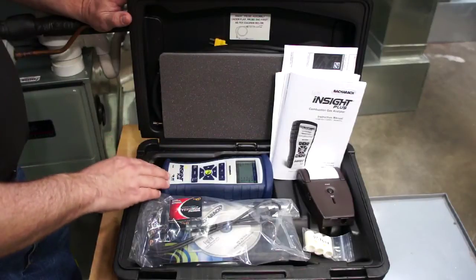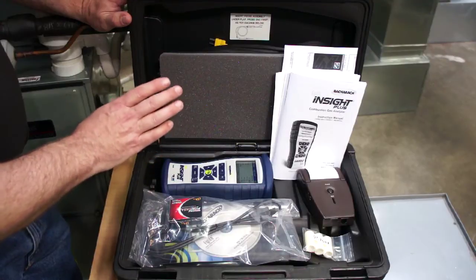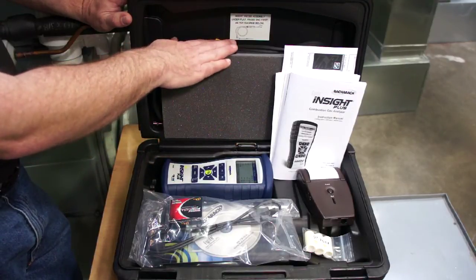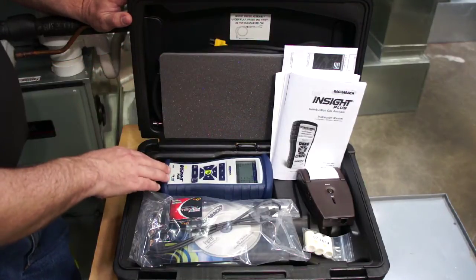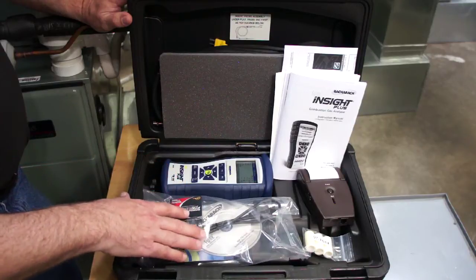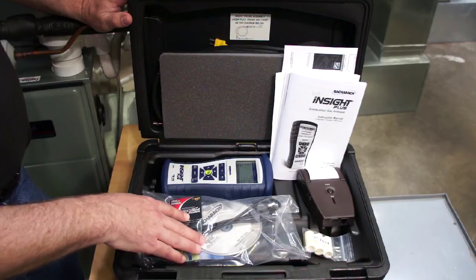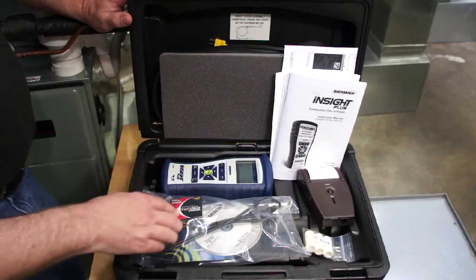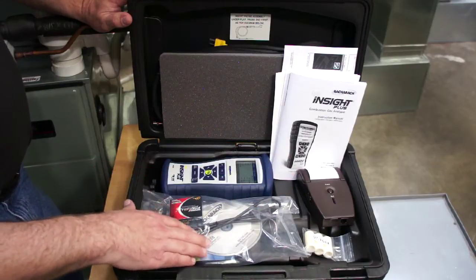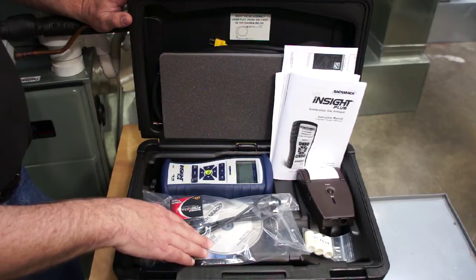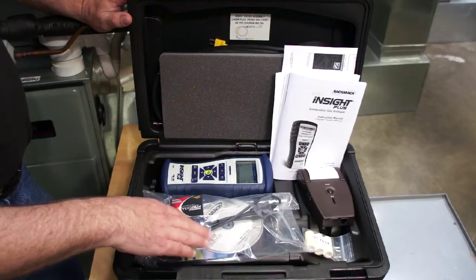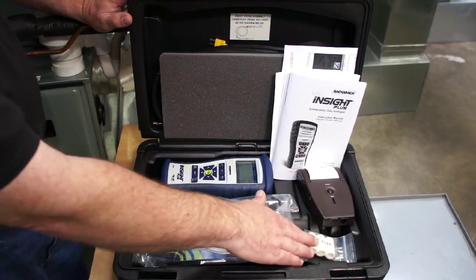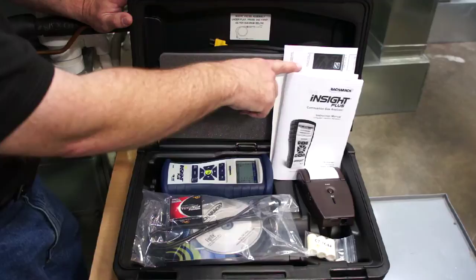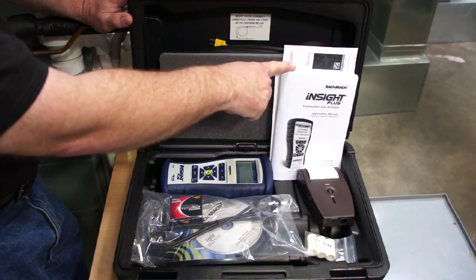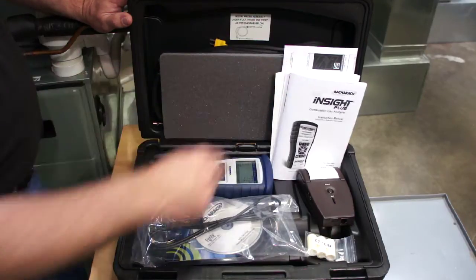So when you get the INSIGHT Plus, it comes in a really nice hard case. You got a storage place up top for your probe assembly, storage place for the instrument. You're going to get your two sets of batteries, one set for the printer if you get a printer kit, and one set for the instrument. And it also comes with software to manage the data and also configure the instrument. So you get a USB cable, some particulate filters for the water trap, and a set of instructions on how to configure and operate the instrument.